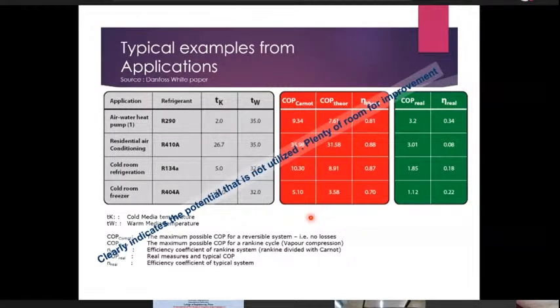However, for reasons of impact on global warming, each of the refrigerants also has a global warming potential. And R410A has a global warming potential higher than the refrigerant that it replaces, R22. So there is going to be engineering development work because of the need to transition from high global warming refrigerants to low global warming refrigerants. Part of the switch from R410A to R32 has taken place because of this understanding that R32 as a refrigerant will have a lower global warming potential than R410A.